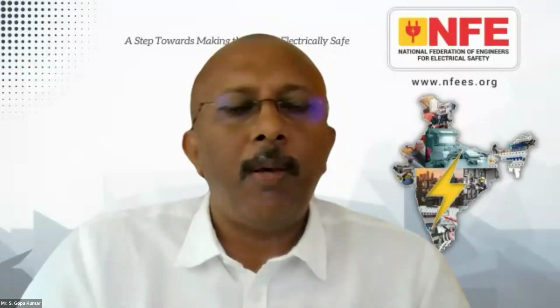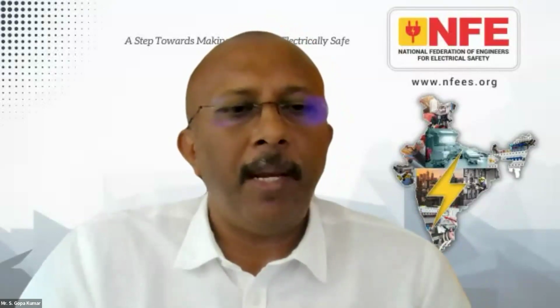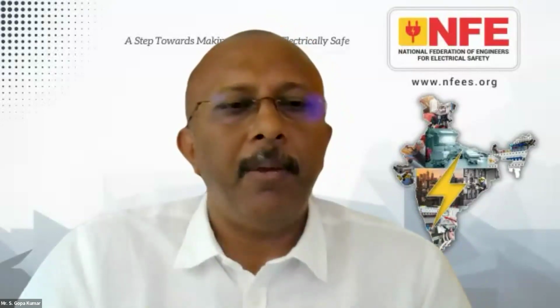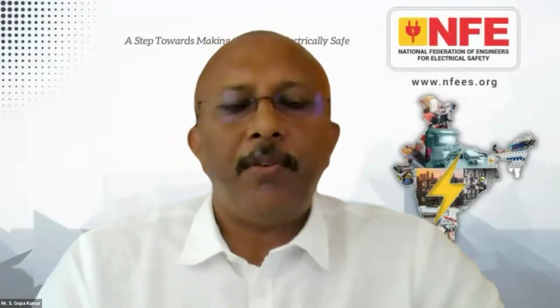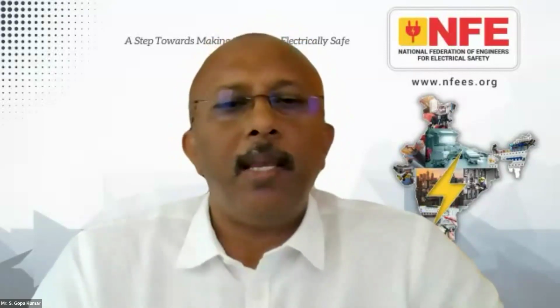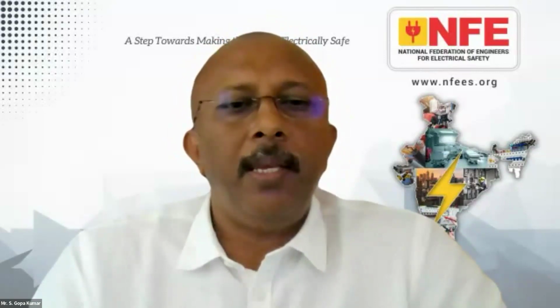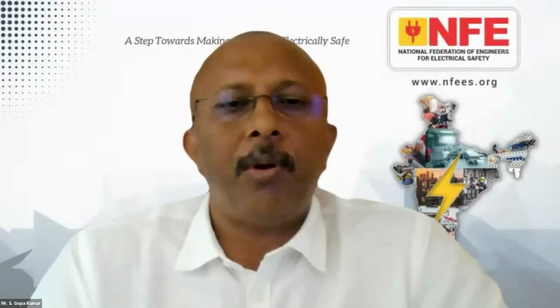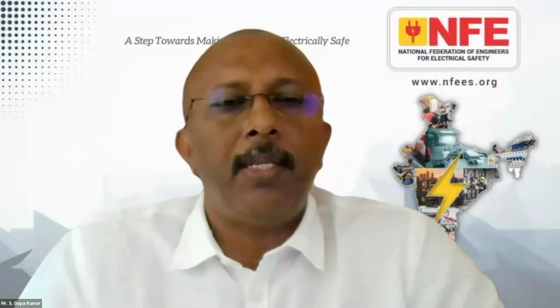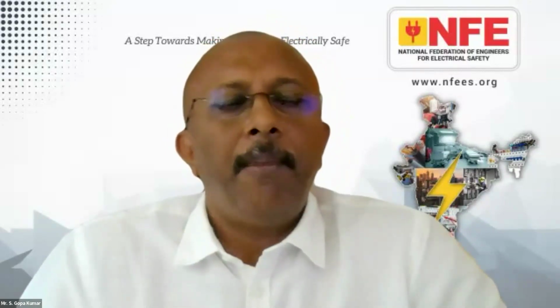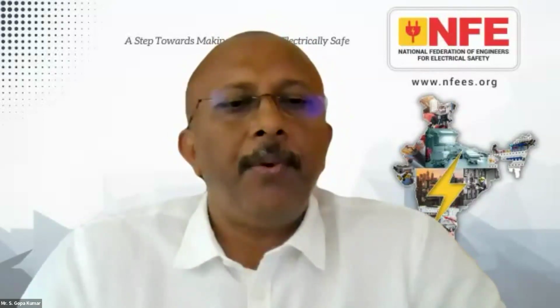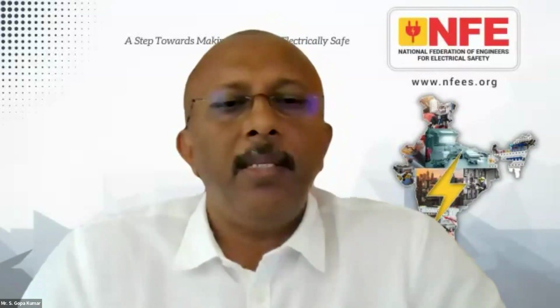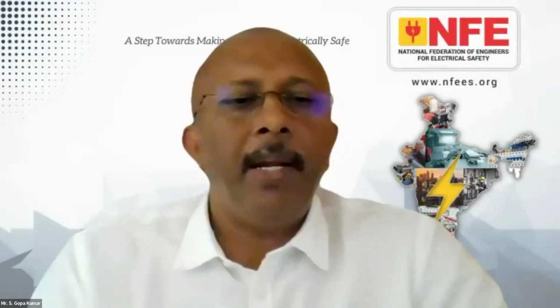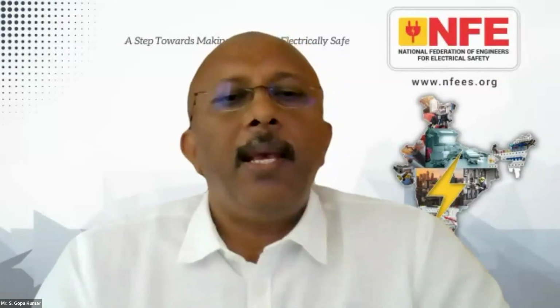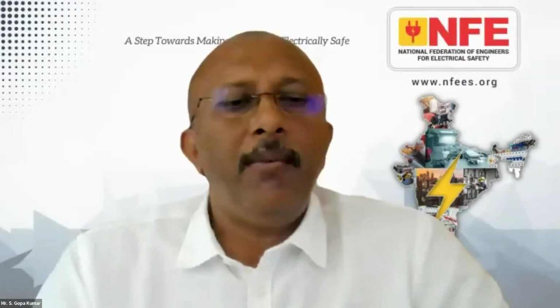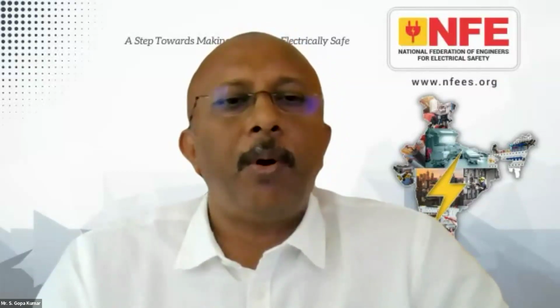An earth electrode may be required. It's not mandatory. May be required in the sense, first of all, to protect from shock and arcing, you must interconnect all metal objects, or technically what we call simultaneously accessible metallic parts, which must be bonded together. That means you have to have a very good equipotential bonding inside your building, which is a mandatory requirement. An earth electrode in soil, if you have one, you connect to the equipotential bonding system.